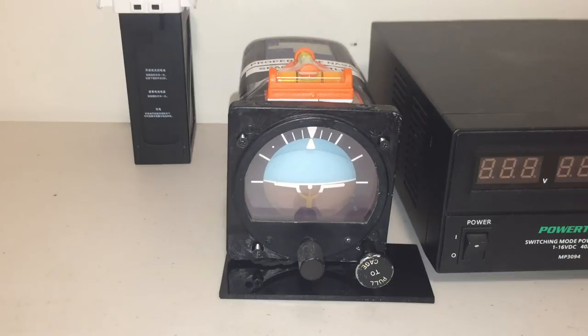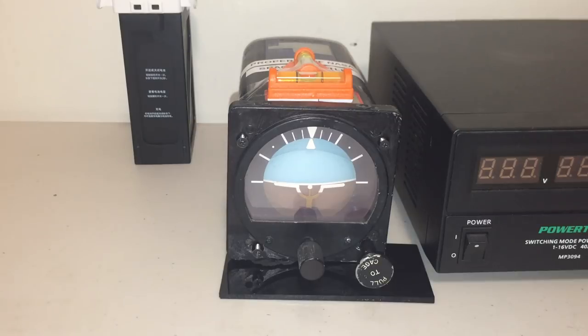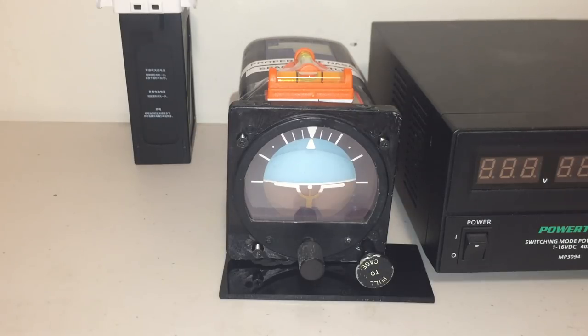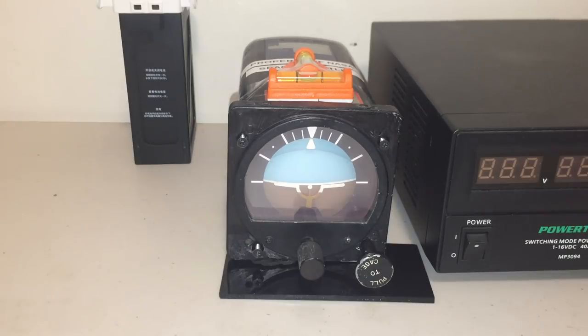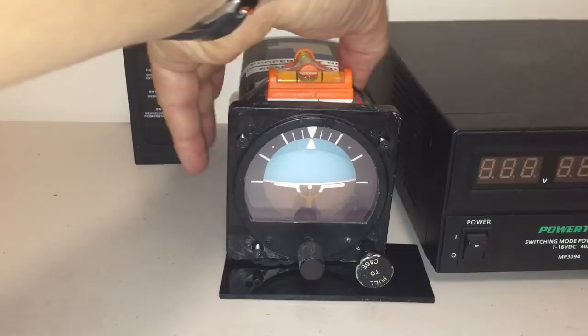So you can see once again, it doesn't really matter what the original starting position is of the gyro or the case. The gyro will, when left to its own devices, always find true level. So that's running fine now.